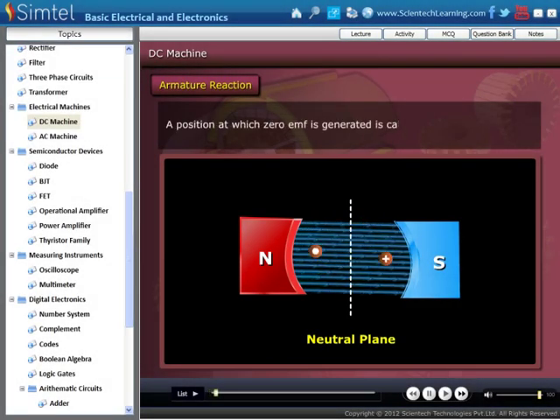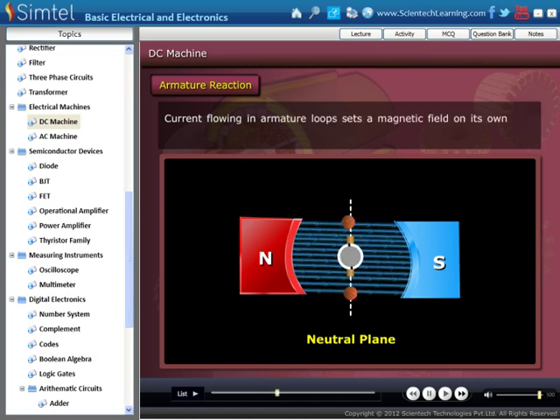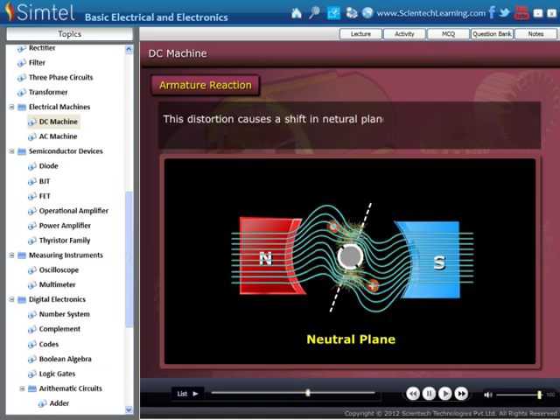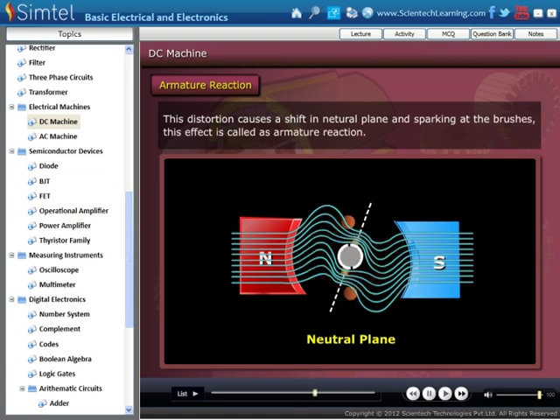Here we study about armature reaction. An important problem in the design of DC machine is prevention of sparking. A position at which zero EMF is generated is called the neutral plane. Current flowing in the armature loops sets a magnetic field on its own. This field interacts with the main magnetic field and distorts it. This distortion causes a shift in neutral plane and sparking at the brushes. This effect is called armature reaction.